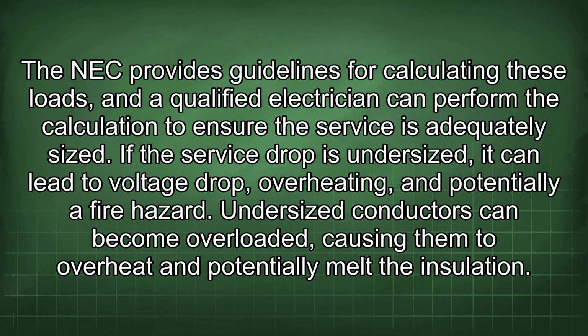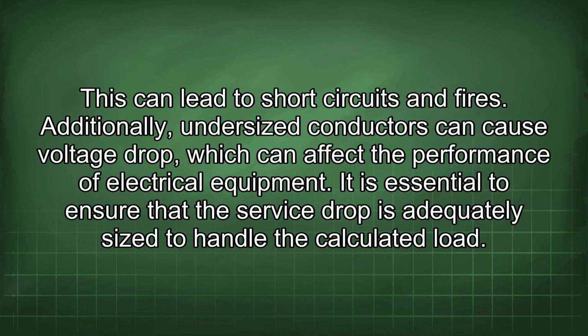The NEC provides guidelines for calculating these loads, and a qualified electrician can perform the calculation to ensure the service is adequately sized. If the service drop is undersized, it can lead to voltage drop, overheating, and potentially a fire hazard. Undersized conductors can become overloaded, causing them to overheat and potentially melt the insulation. This can lead to short circuits and fires. Additionally, undersized conductors can cause voltage drop, which can affect the performance of electrical equipment. It is essential to ensure that the service drop is adequately sized to handle the calculated load.